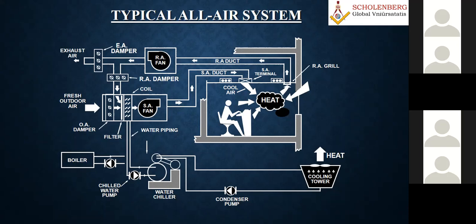Now you cannot put one air handling unit which is common for the operation theater and the same thing common for the administrative area or corridor area, isn't it? Okay. So this is what the specification as per the ventilation says, how much percentage.